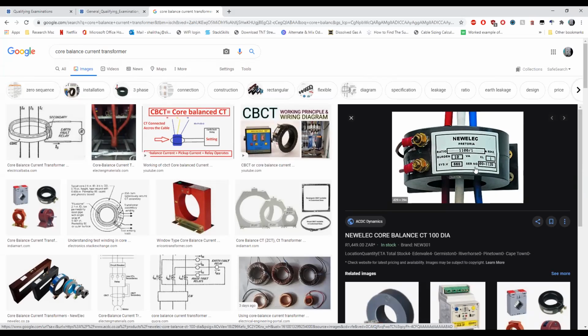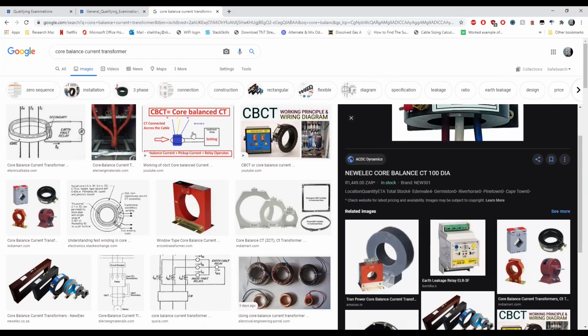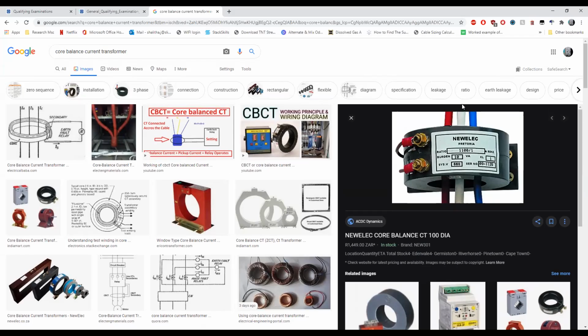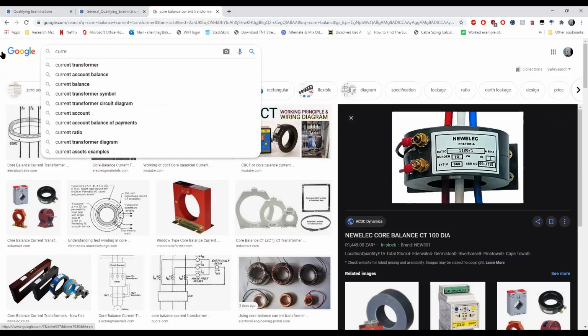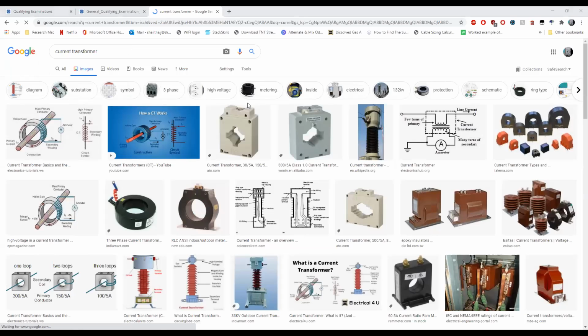So this is a CBCT. I just found this image on the internet. So this is what it looks like. It usually works on the principle of electromagnetic induction. When conductors are carrying current, there are electromagnetic fields around them. When you have three phases, these electromagnetic fields cancel out and nothing comes to the CBCT. So they use that principle to detect any imbalance in the phases. And usually, with current transformers, see, these are current transformers, only one wire goes through them, so they are used to measure the current through that wire. If you have seen non-invasive current sensors, these are the things we have in those sensors.